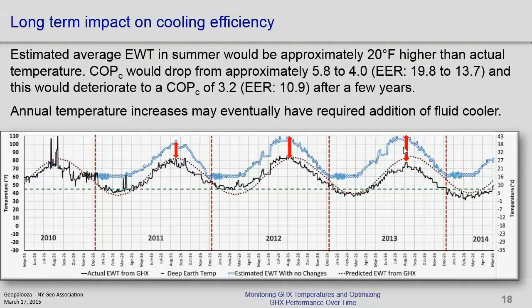So what happens then, the coefficient of performance, or the energy efficiency ratio in cooling, gets worse and worse. Starts deteriorating, and eventually it would have probably cost them close to $100,000 to put a fluid cooler in at that point. So what happens then is the client thinks, well, why did we spend this extra $150,000 on the ground loop? These things don't work, and we're not going to put it in our next building, and we're going to tell all the people that we know that these things don't work.